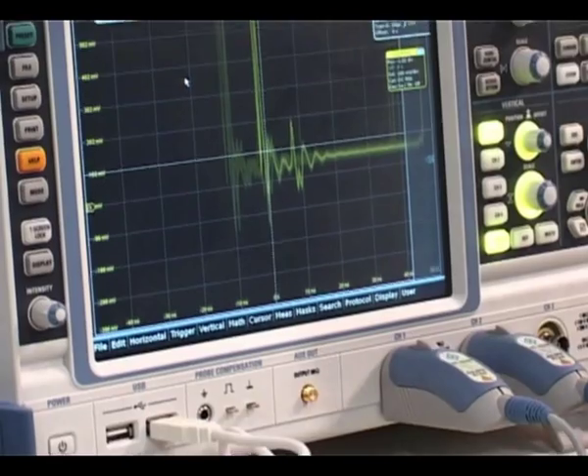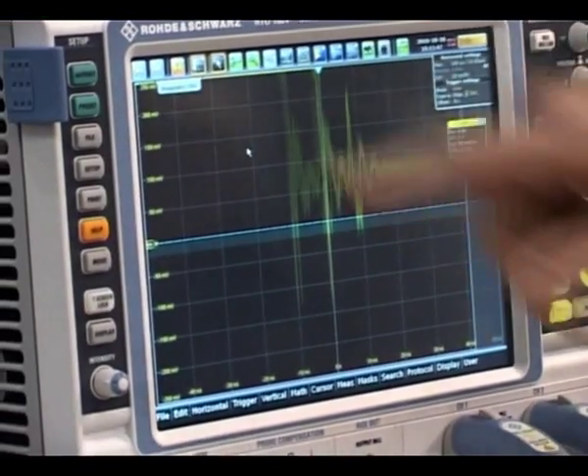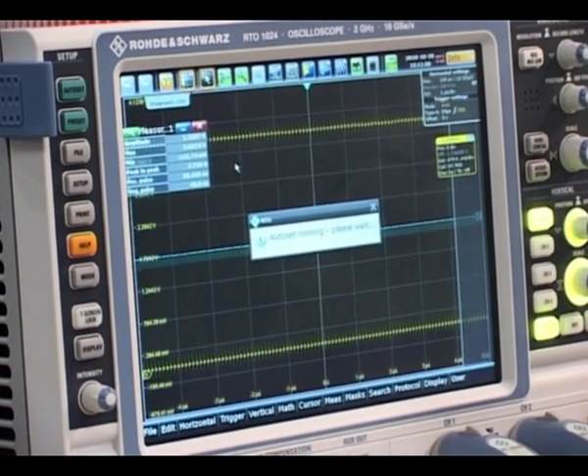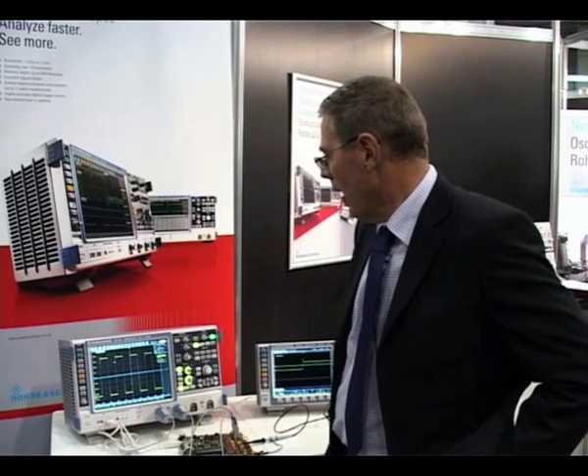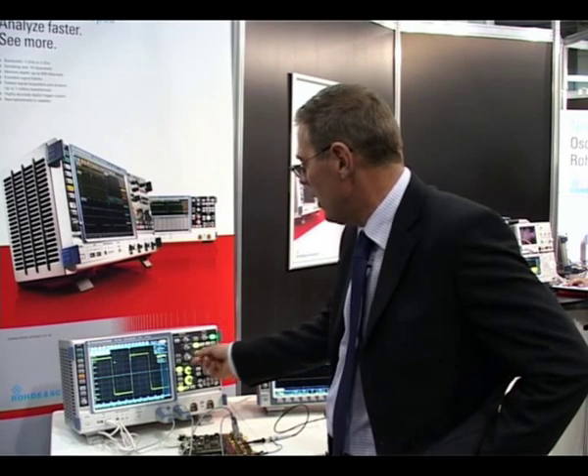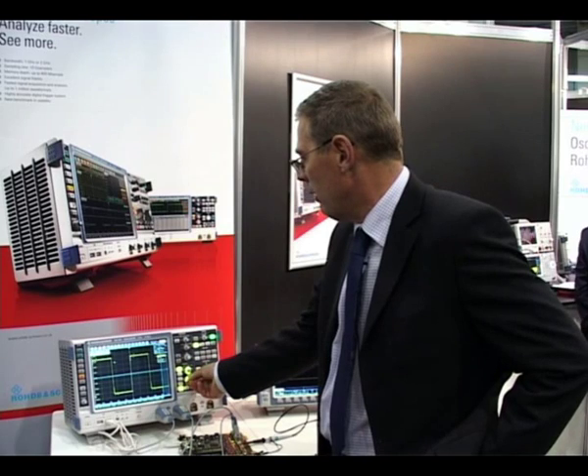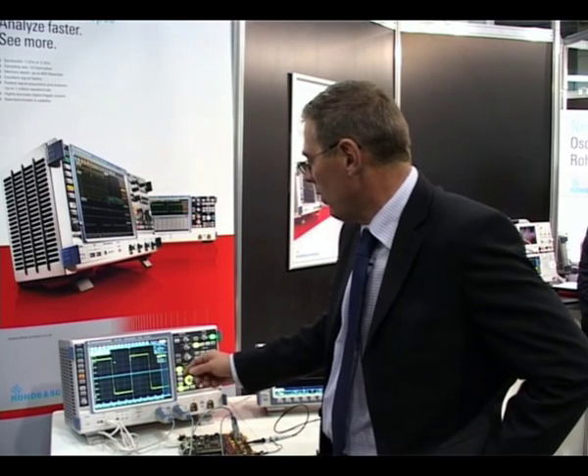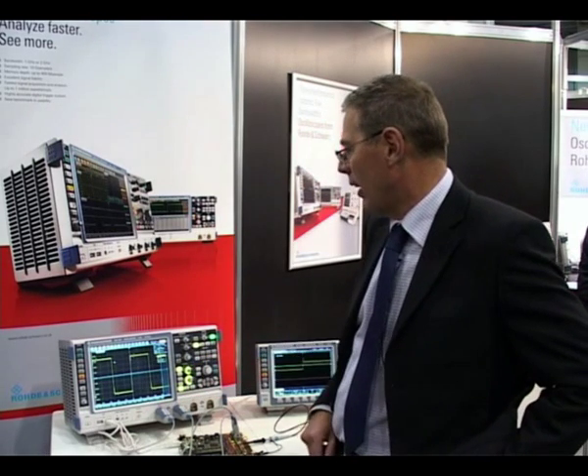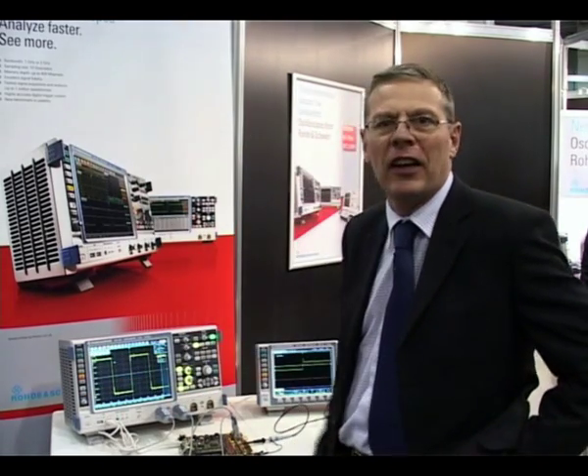So the first thing we'll do is we'll assume that we don't know anything about the signal here. We'll do an instant preset and we'll go and press auto set to actually grab the signal on the oscilloscope and the signals come up on the screen there. Quite easily we can change the time base per division and the actual size of the waveform and we can see straight away that on this particular signal if you wind the brightness up there's the odd flicker.